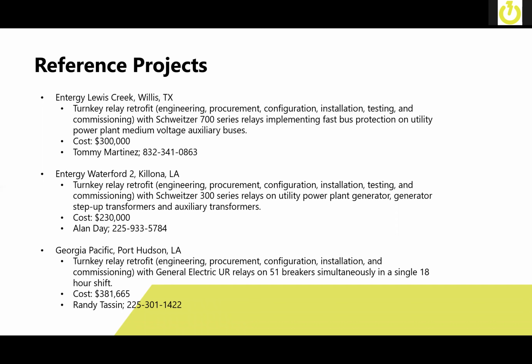Georgia Pacific, this is one where the customer came to us and they had a very, very limited time frame to do the relays. We were able to do a turnkey relay retrofit, engineering, procurement, configuration, installation, commissioning, etc., with General Electric UR series relays. We were able to complete 51 breakers simultaneously in a single 18-hour shift. I'll be honest with you, that was a little bit of a challenge trying to get all that done. It was multiple crews working in multiple locations, and it was a huge logistical challenge to do all of that at one time. The cost was approximately $381,665.